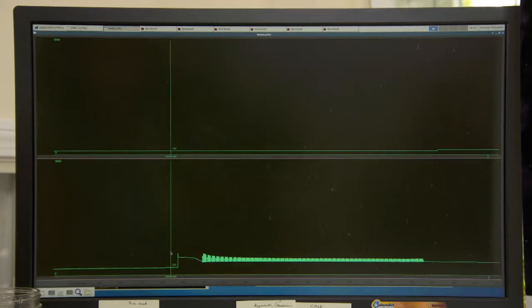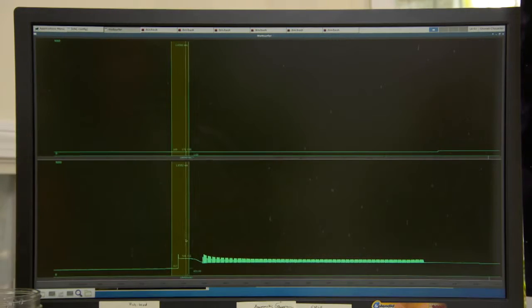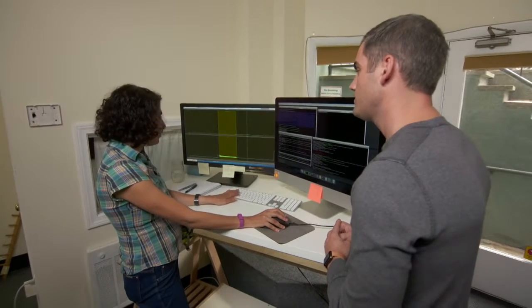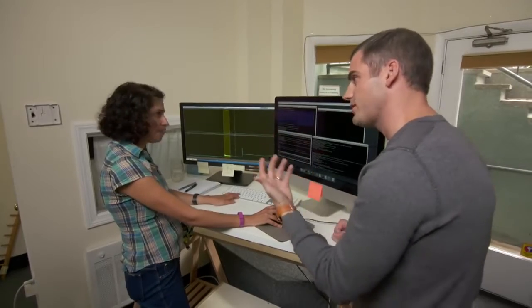Okay. Here, the furnace starts with an inducer motor turning on, and that blows the gas in the direction of the flame. This furnace is a spark igniter furnace, and right here is the spark igniter turning on. Gotcha. And people who own spark igniter furnaces can also hear it ticking. So that's that tick, tick, tick as it starts up.